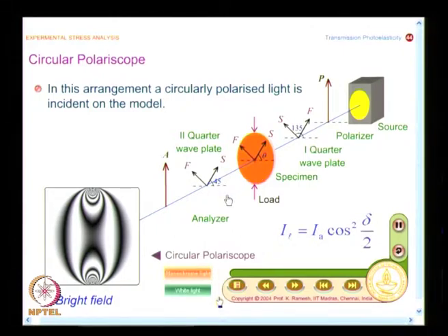And this is the reason why in conventional photoelasticity people never bothered about calibrating a polariscope. Calibration of model material everybody knows. The moment you come to digital photoelasticity, I must also calibrate the polariscope to the mathematical expression I have. If in the mathematical expression I have the slow axis at 135 degrees, I must adjust my polariscope until my analytical expression and what I see in the experiment match one to one. Why is this so?